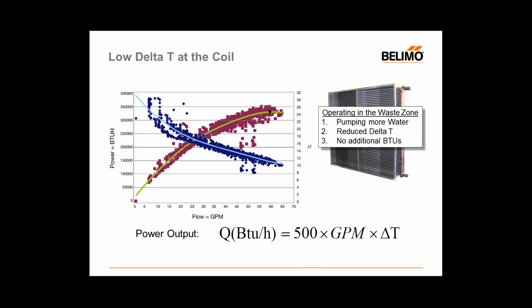So if we go ahead and take a look at a point here, and that's right about 58 gallons a minute or so, and then we extrapolate a line horizontally to all of the points in this point cloud that produce the same amount of BTUs as we did at, say, 58 gallons a minute, you can see that at some point during our heat exchange process, we did that amount of cooling at about 47, 48 gallons a minute, and sometimes we did it at as much as 65 gallons a minute. So we had this range between, say, 47 and 65 where we were able to produce the same amount of cooling in that space.